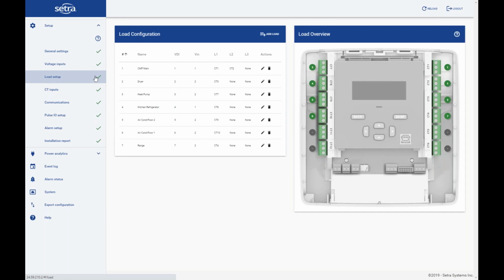Next, we have a load setup. So you can name the load something that means something to you. And we also number the loads in order that they are added to the meter. You can see the voltage input that it's referenced to, whether it be 1 or 2, based on how it's hooked up in that particular panel, as well as the different CTs that are tied to that specific load, depending on what type of load that it is.